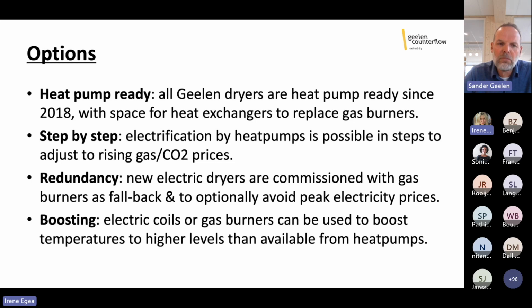And finally, boosting electric coils or gas burners can be used to boost temperatures to higher levels than those that are available from our current generation of heat pumps. So the heat pumps we are using now are somewhere in the 120-130 C range, and some of our processes require 140-150. So you can then add additional temperature to the air by boosting it with either electric coils or gas burners. Next slide, please.